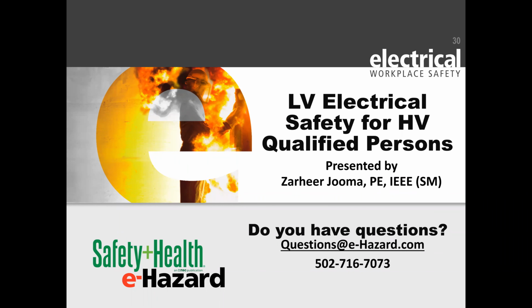But I'm going to say categorically, no. If a person is not low voltage task qualified or low voltage qualified, they cannot use a basic meter. And when you say a basic meter, I hope you're not talking about the pencil kind of non-contact tester, because those are not allowed by NFPA 70E, the consensus standard. And oh my gosh, you would be in so much trouble if you're using that for the purposes of lockout, tagout.